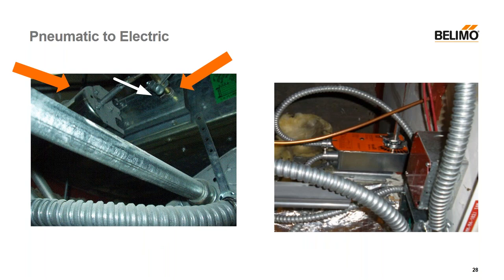The pneumatic to electric conversion: at the top left there's a pneumatic actuator held on a bracket, and the middle white arrow is pointing at the damper shaft. You're going to not try to replace the motor or do a linear push-pull thing with a crank arm. As shown in the right picture, you'll simply direct couple the motor right over that existing damper shaft. You might notice we left the pneumatic bracket because it was a good place for mounting the anti-rotation strap.